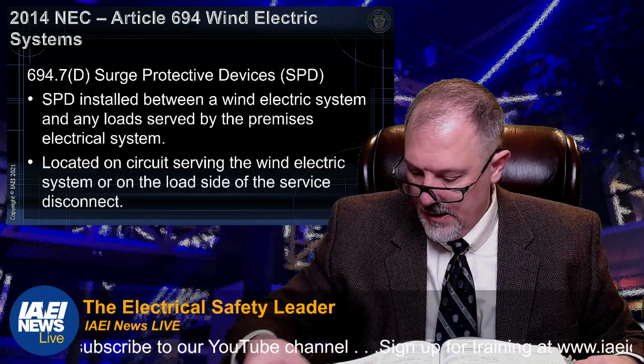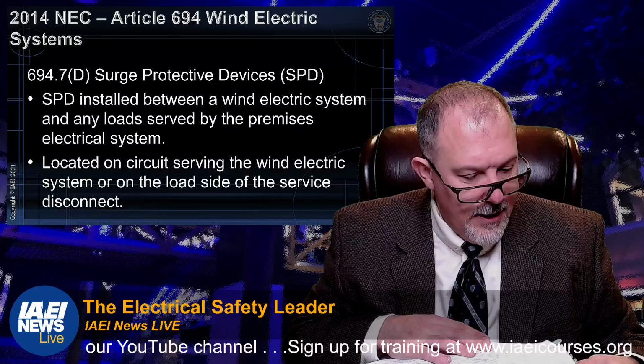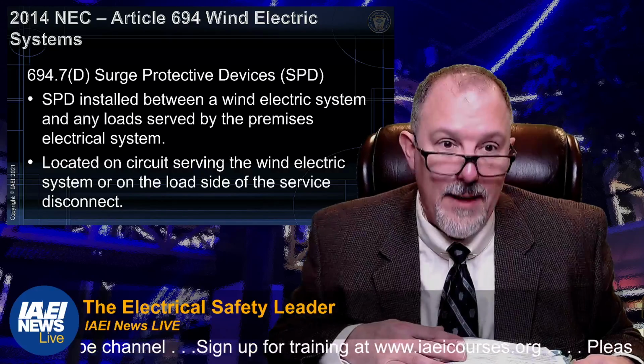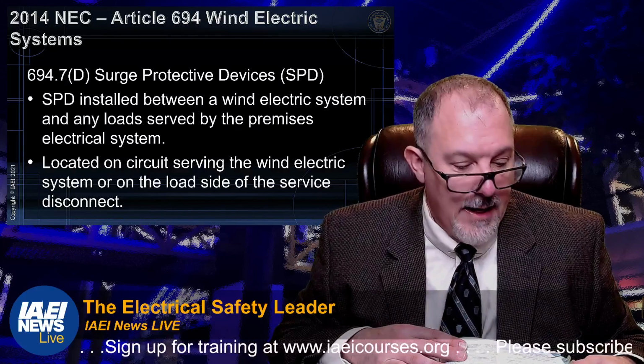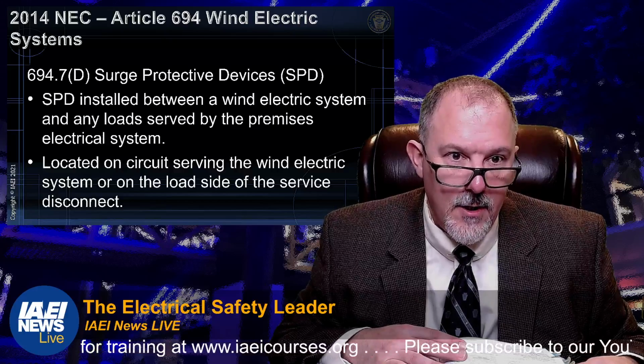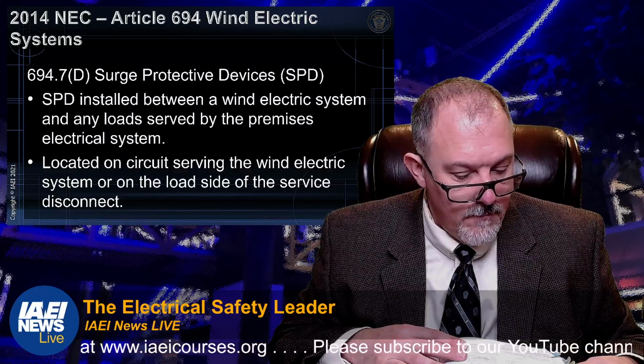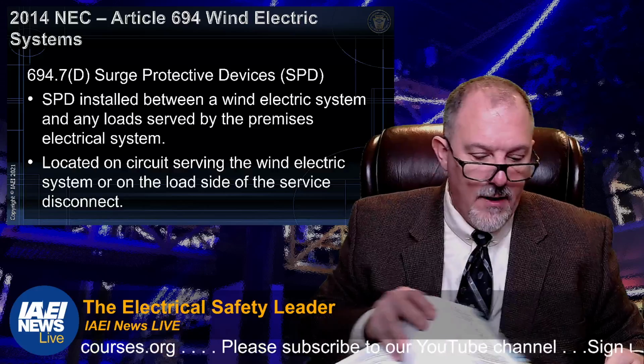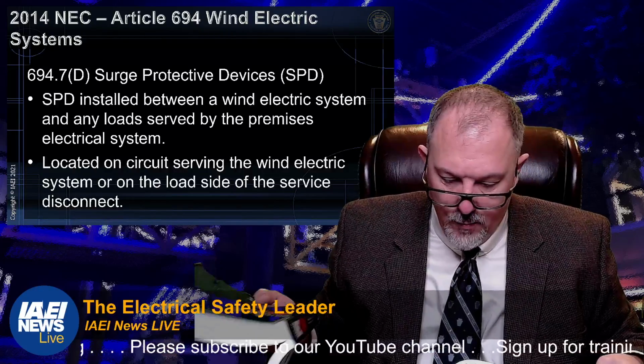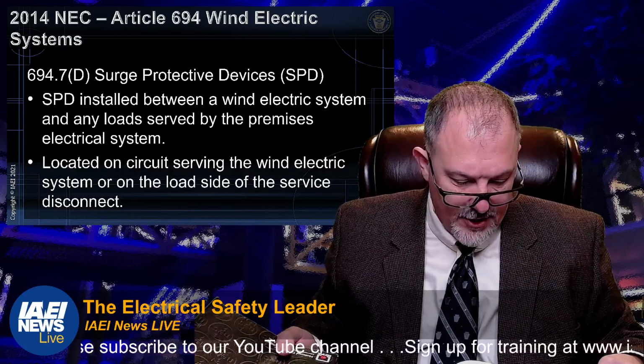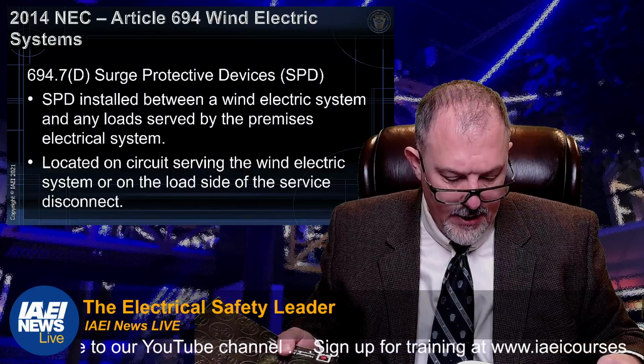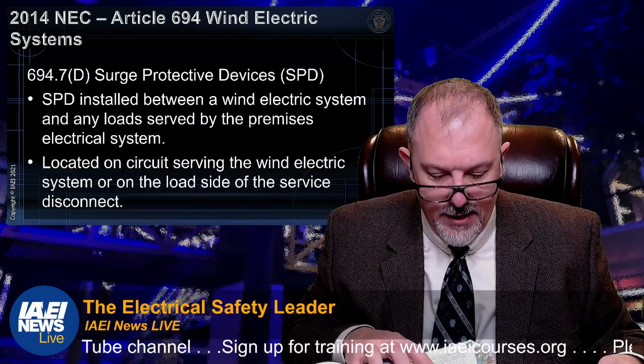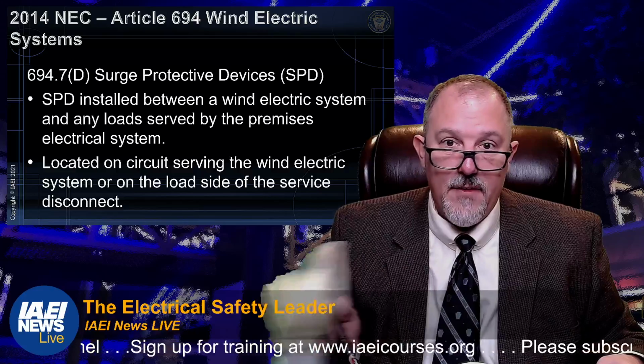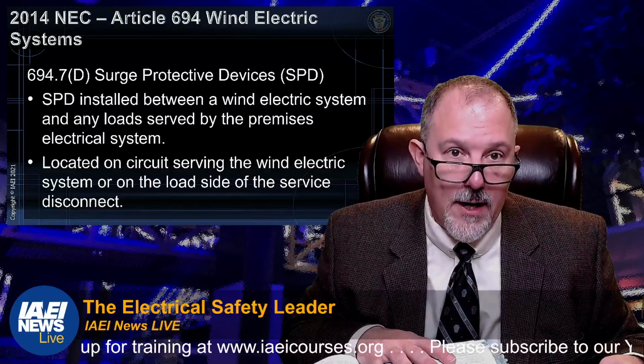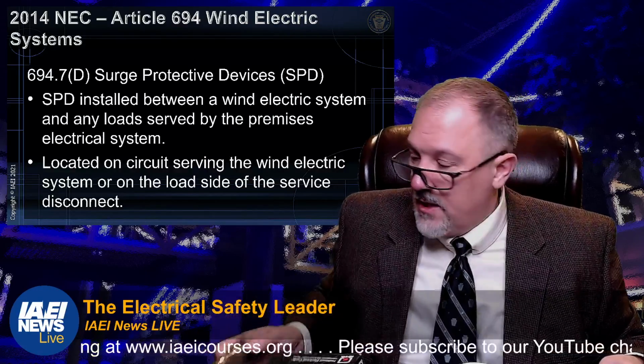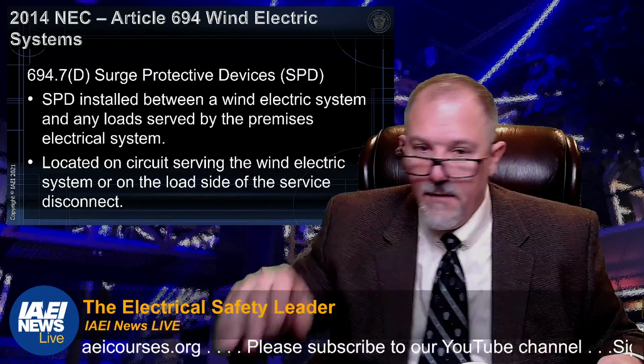694.7 is installation. And D, surge protective devices. So it's been in there a while. I think what happened here was Article 285 in the 2020 code. We had to reference a different section. That was the only change that we made. Article 242 instead of Article 285. This is the 14 code. So surge has been required in Article 694 for a little bit now.